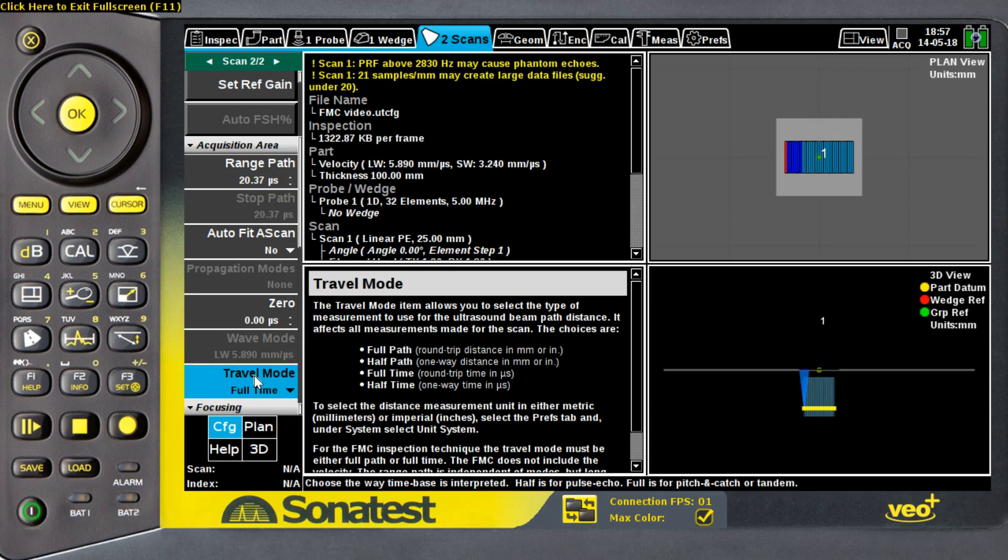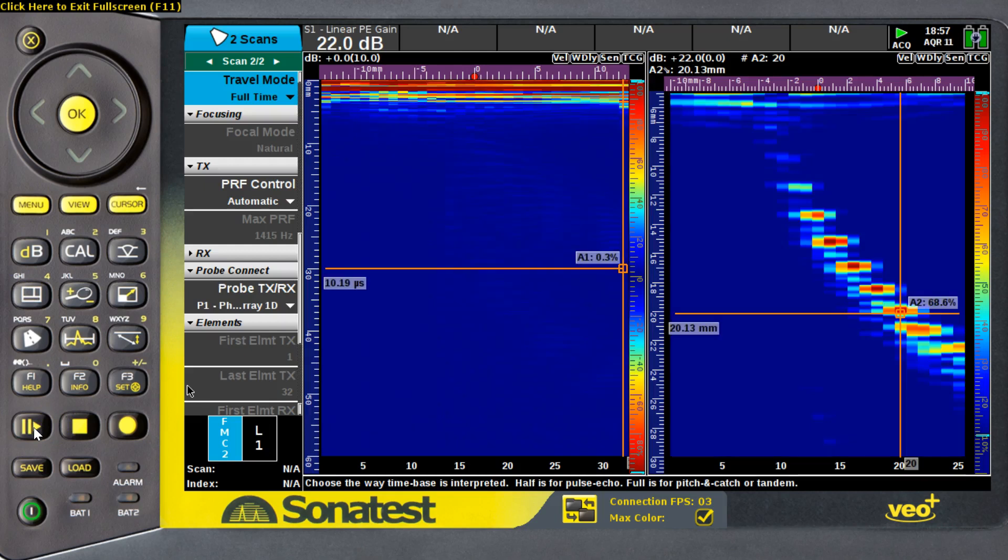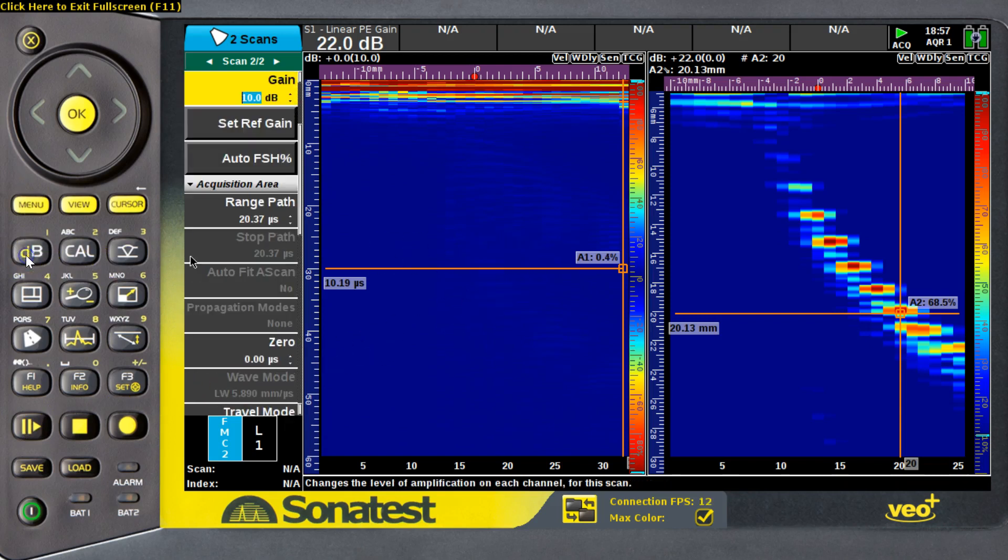Now, after setting my travel mode into full time, I can start the acquisition. As we can see on the right, I have my linear scan and the defects, while on the left, this is my FMC scan that runs concurrently with my Phased Array scan.